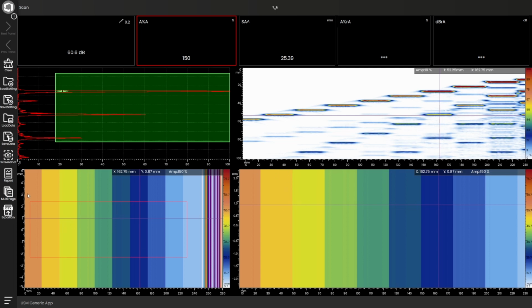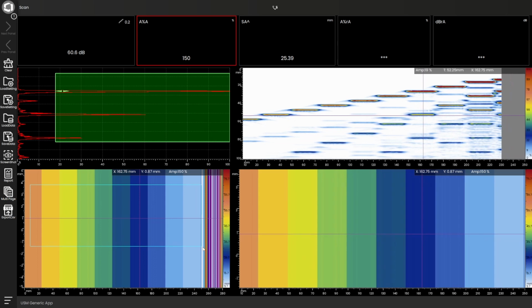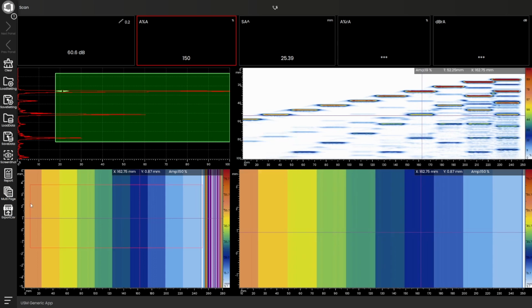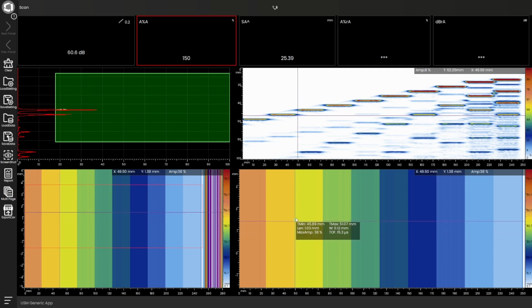So if I stretch my measurement box out to include on the active the entire area that I scanned nicely, we get a good look at our block. Now, on the active C-scan and B-scan, I have measurement boxes that are available as well. So if I click and drag, and this would be the same thing as placing my finger on the instrument, I can touch and drag a measurement box. And by adjusting the edges of the measurement box, I get some interesting information in the little window that pops up.